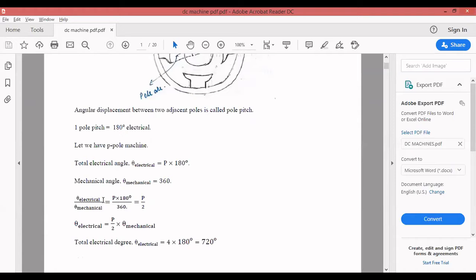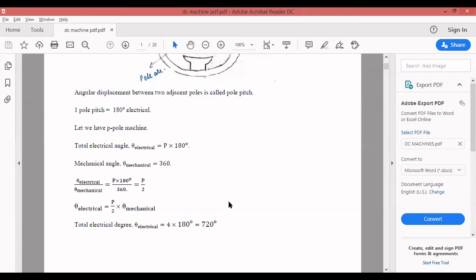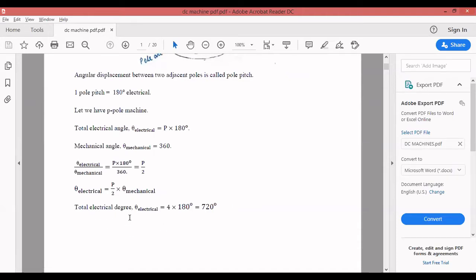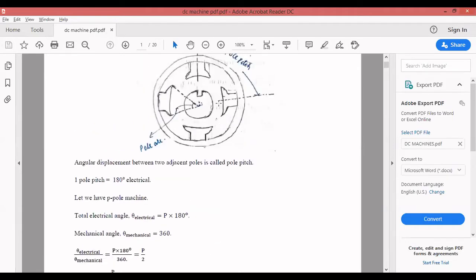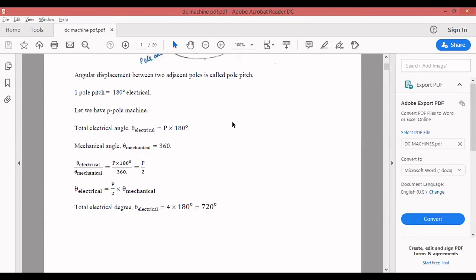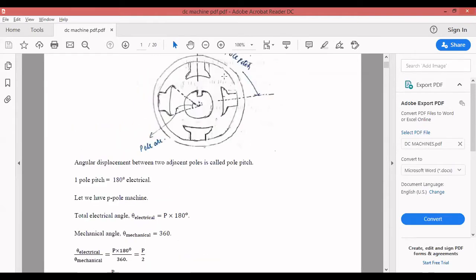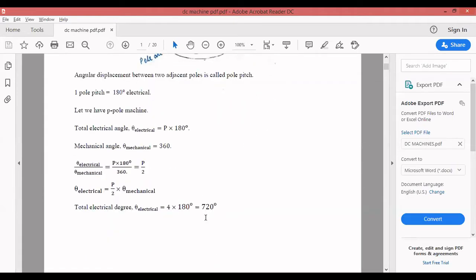Theta_electrical divided by theta_mechanical — how do you work this out? Based on the number of poles: P into 180 divided by theta_mechanical, which is 360. Solving this gives P by 2, so theta_electrical equals (P/2) into theta_mechanical. For four poles: total theta equals 4 into 180 degrees electrical, which is 720 degrees electrical. In mechanical terms it is only 360, but in electrical terms it is 720, based on the number of poles.